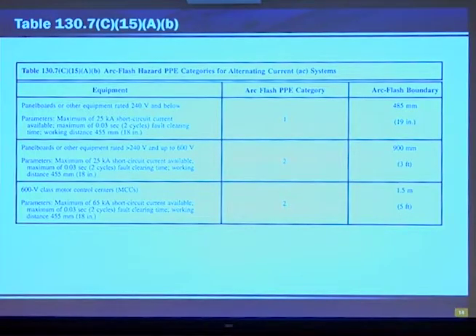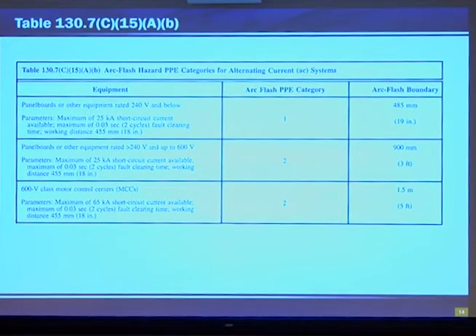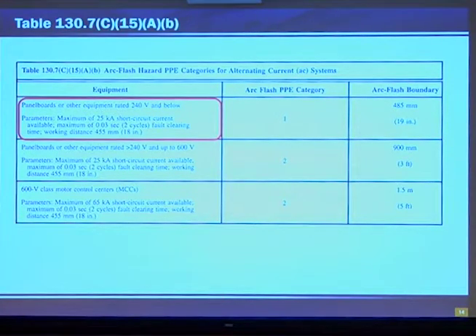So let's use that same example. Our circuit breaker's bad, we need to replace them. So say we were in a traffic signal, it's a 120/240-volt service. So our equipment will be panel board or other equipment rated 240 volts or below. The ArcFlash category would be 1, correct. The ArcFlash boundary will be 19 inches. So it tells us our PPE needed will be 1, boundary of 19 inches.